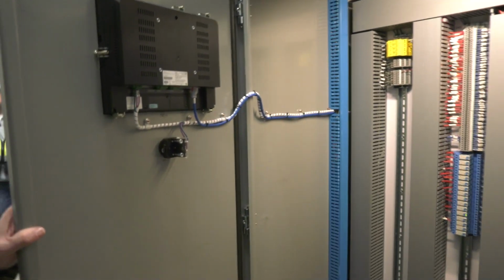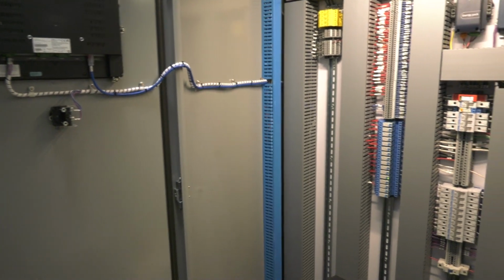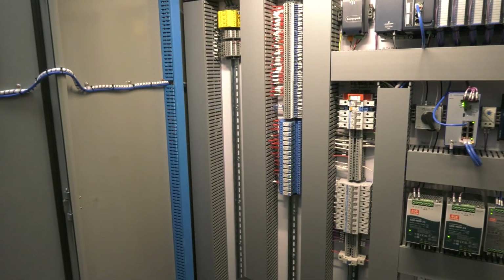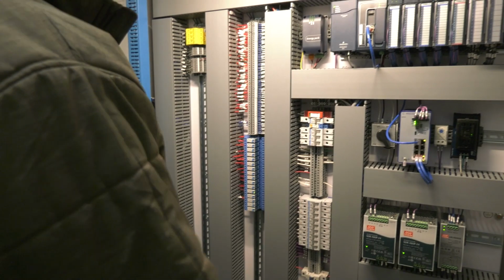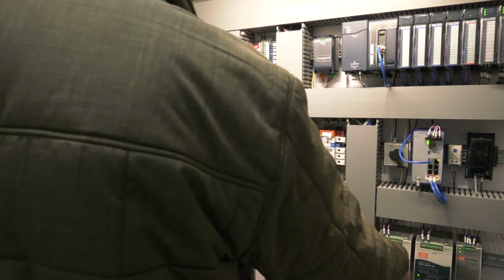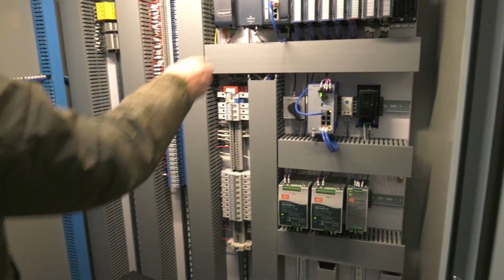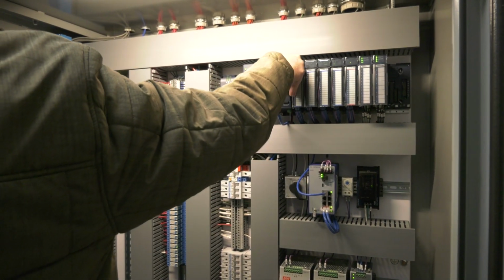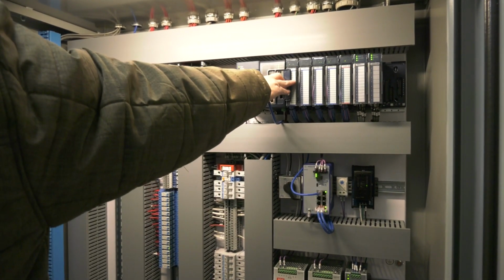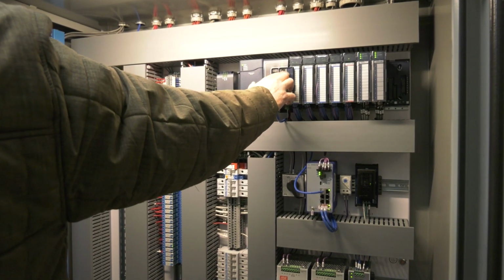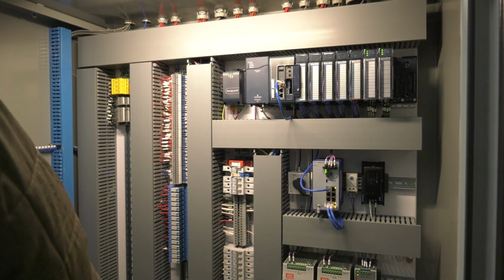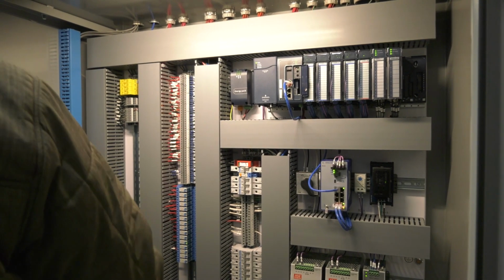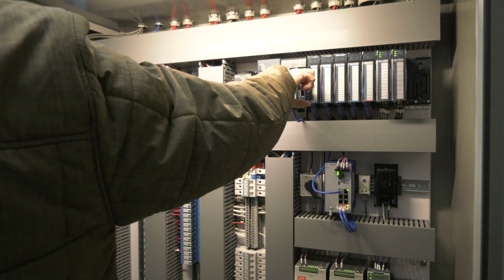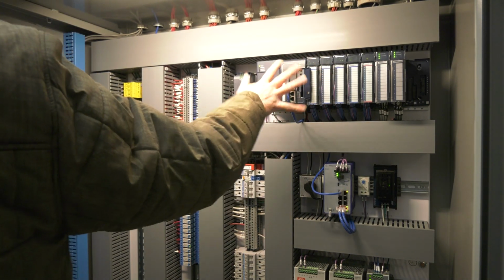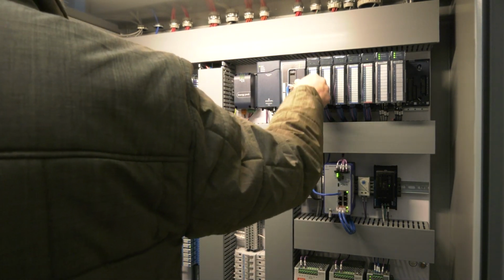All right, so inside this control panel is basically the same thing that we have at central. Power supplies, redundant power supply, PLC, and over here is that switch I was telling you about. Stop, run IO. If they have to replace the processor for some reason and you can't get the CSO to function, you want to make sure that switch is in run IO. So it'll run, you just won't have any IO.